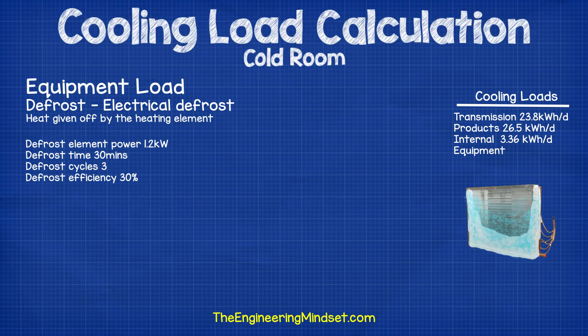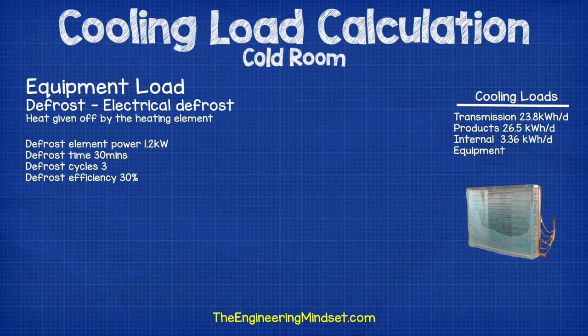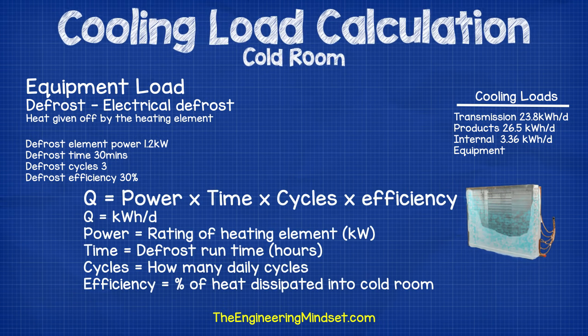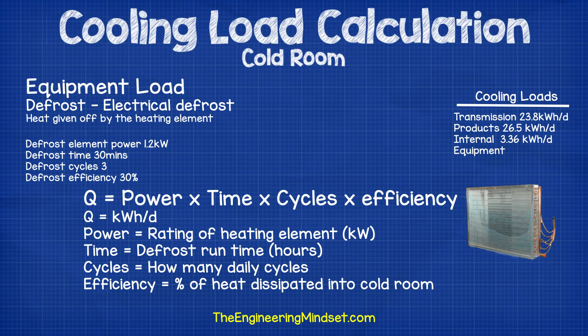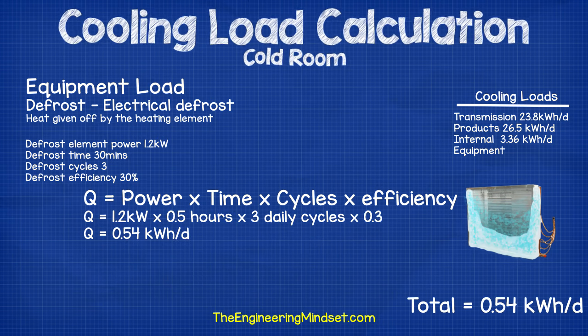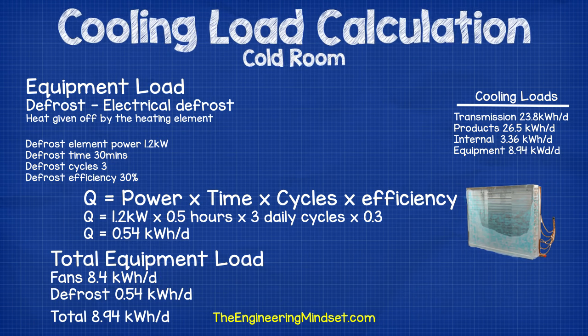Now we calculate the heat load caused by defrosting the evaporator. Our cold room uses an electric heating element rated at 1.2 kilowatts, running for 30 minutes three times a day, with a transfer efficiency of 30% — meaning 30% of the energy consumed is actually transferred into the cold room. Using the formula q equals power multiplied by time multiplied by cycles multiplied by efficiency, this comes out to 0.54 kilowatt hours per day. The total equipment load — fan heat plus defrost heat — is therefore 8.94 kilowatt hours per day.